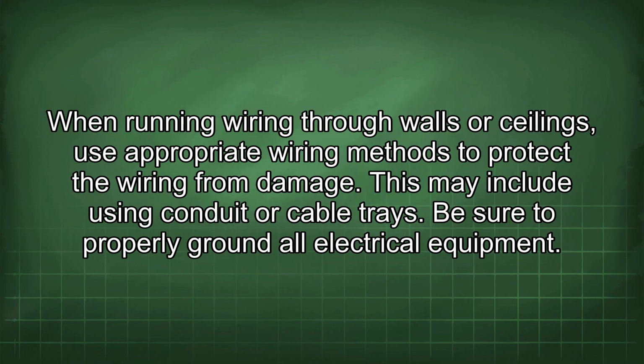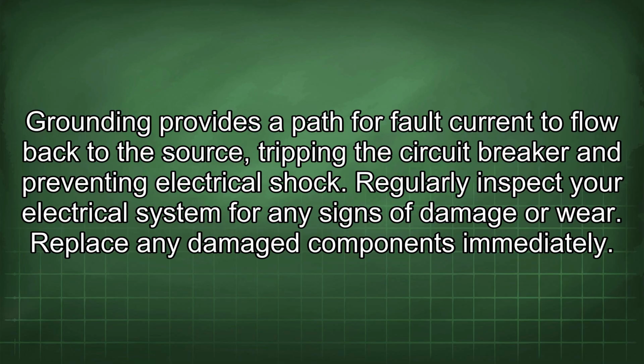When running wiring through walls or ceilings, use appropriate wiring methods to protect the wiring from damage. This may include using conduit or cable tray. Be sure to properly ground all electrical equipment. Grounding provides a path for fault current to flow back to the source, tripping the circuit breaker and preventing electrical shock. Regularly inspect your electrical system for any signs of damage or wear. Replace any damaged components immediately.